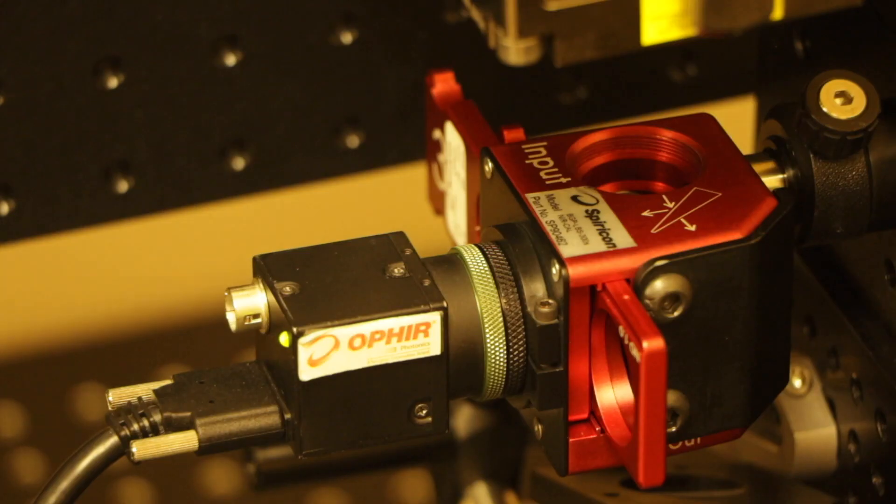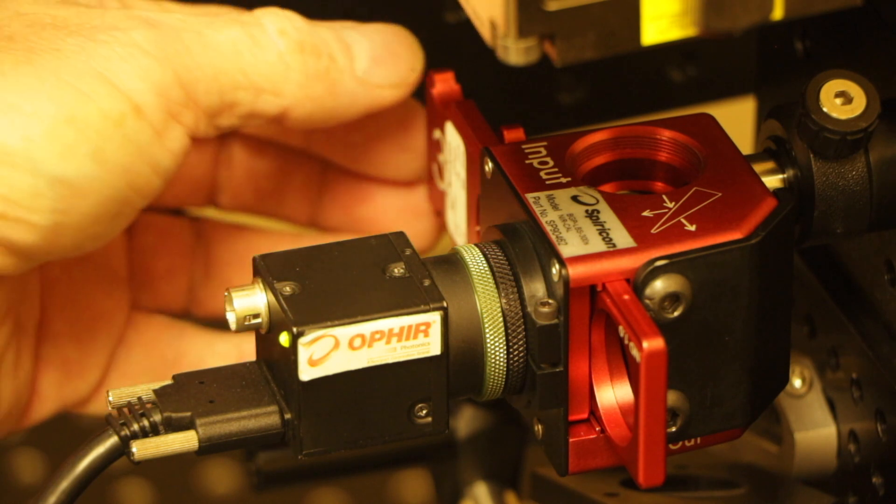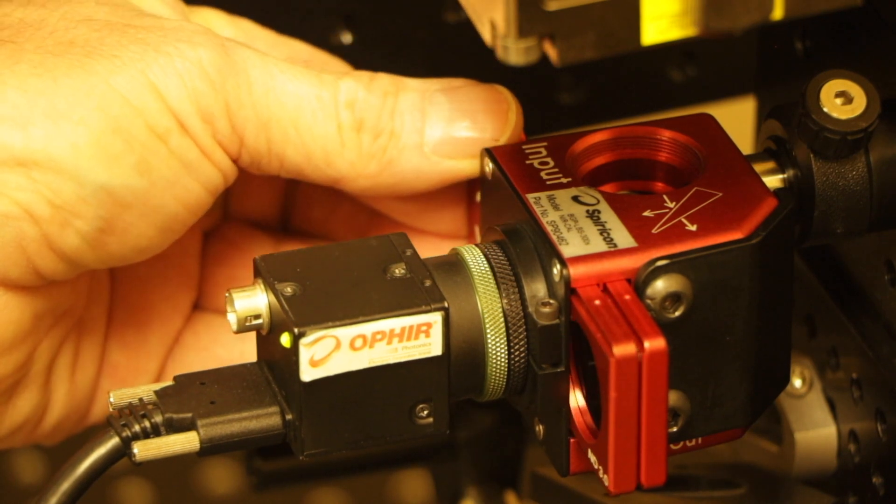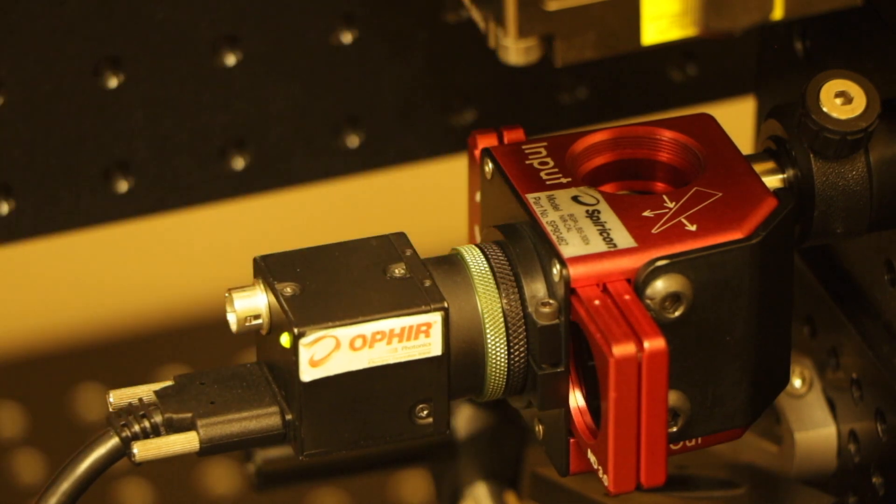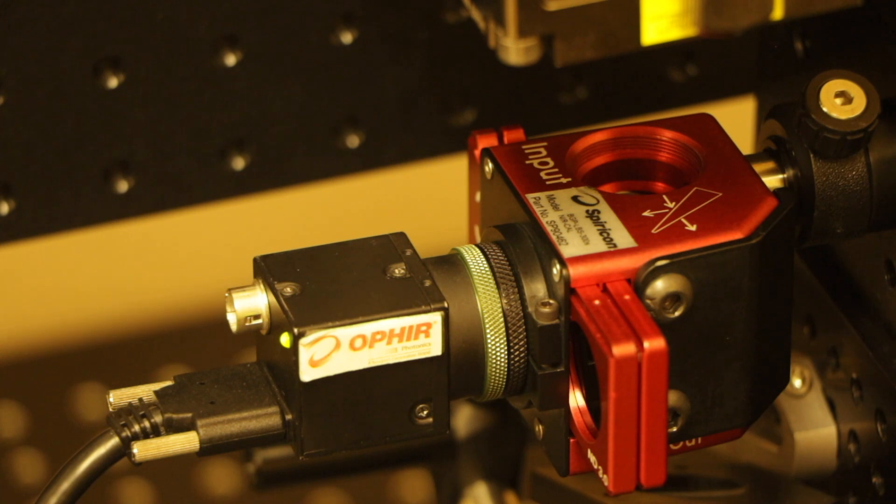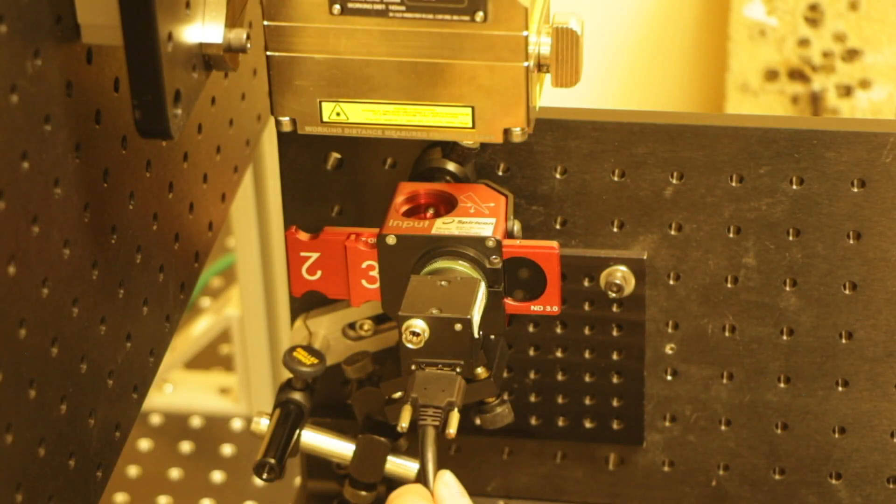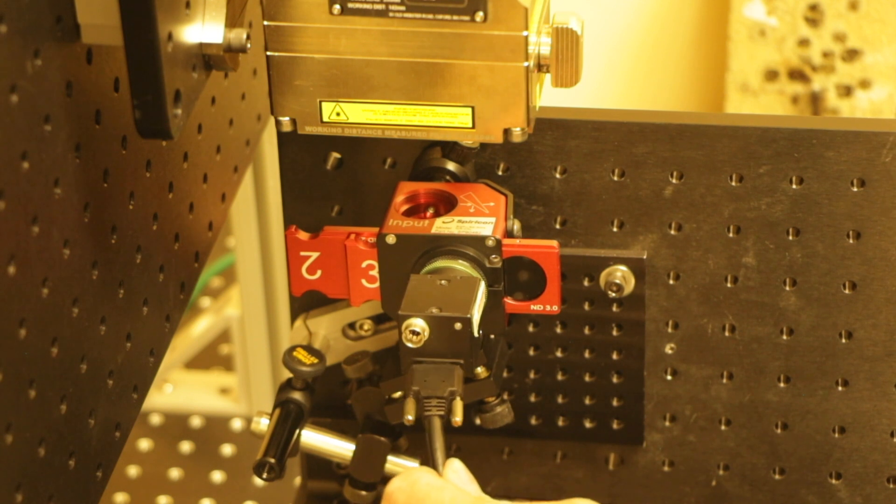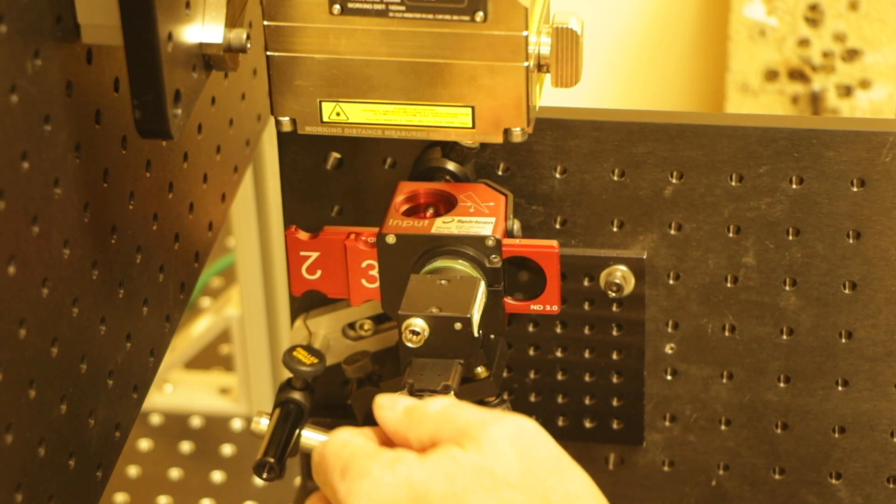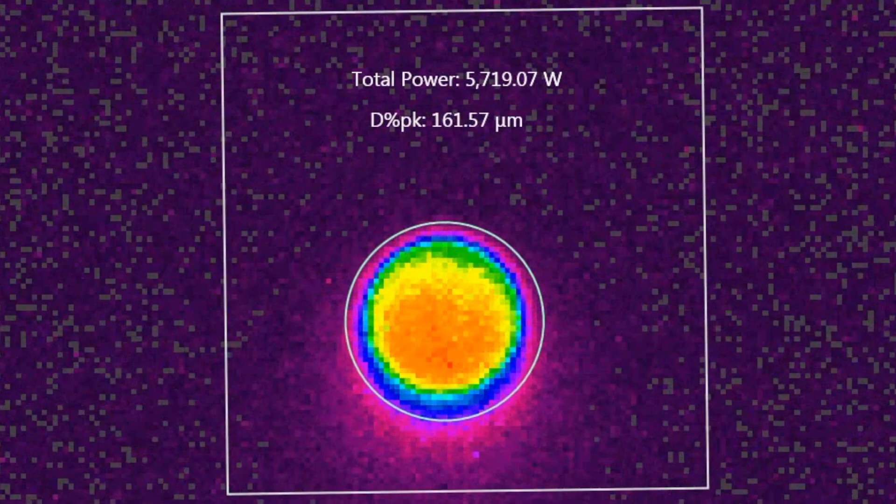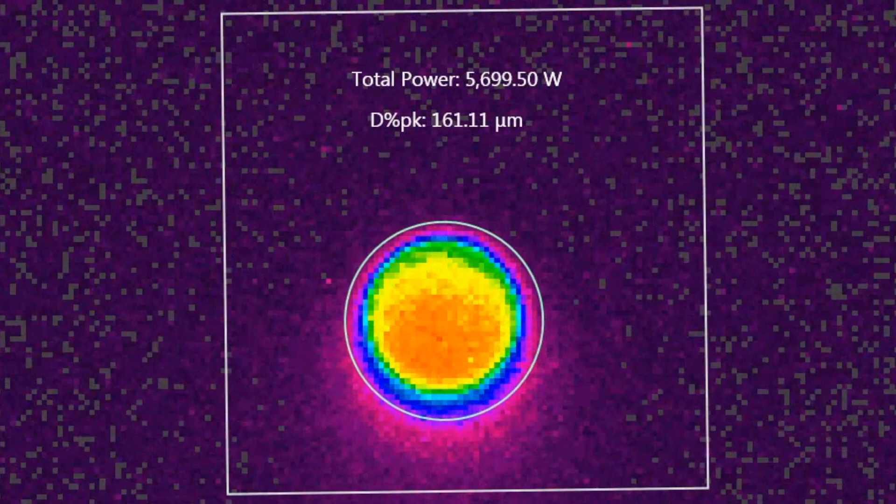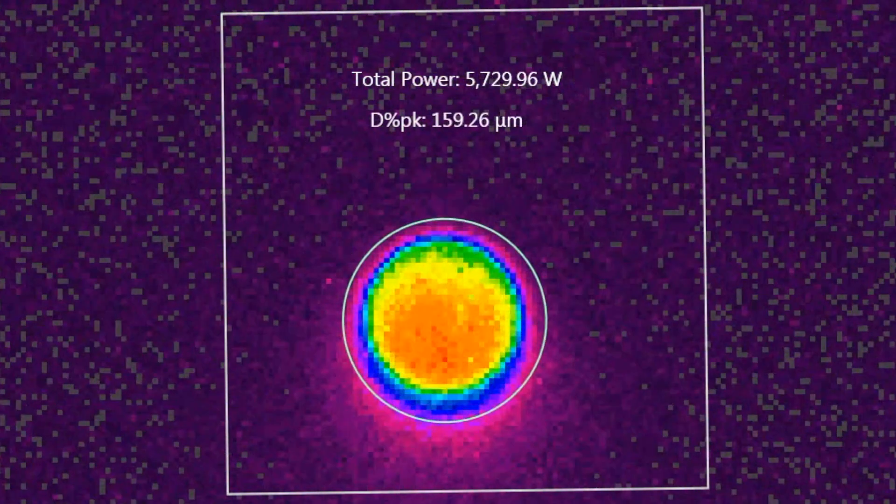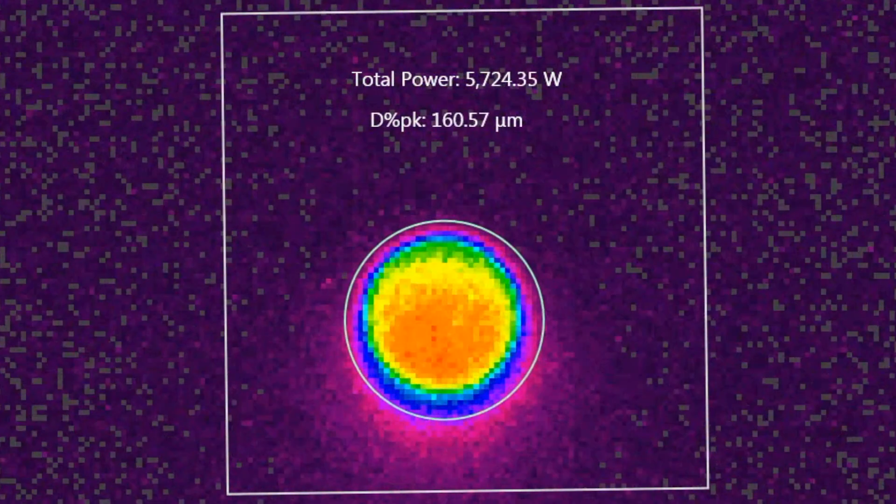With the included ND filters, the LBS 300 HP NIR provides as much as 13 orders of magnitude of optical attenuation. The LBS 300 HP NIR is the first commercially available camera-based laser beam profiling system that can measure the spatial profile of multi-kilowatt lasers independent of wavelength.